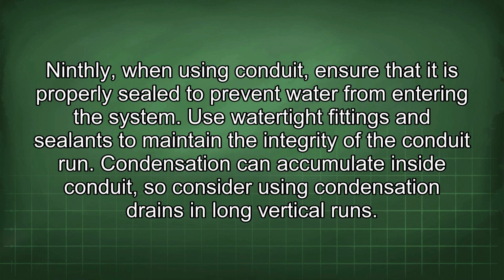Ninthly, when using conduit, ensure that it is properly sealed to prevent water from entering the system. Use watertight fittings and sealants to maintain the integrity of the conduit run. Condensation can accumulate inside conduit, so consider using condensation drains in long vertical runs.